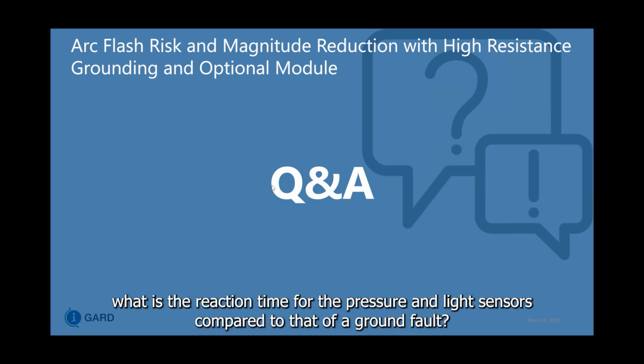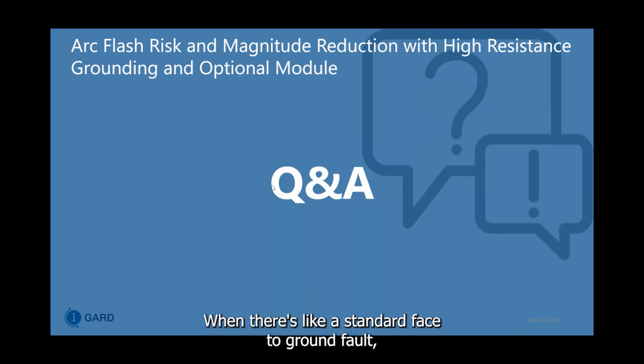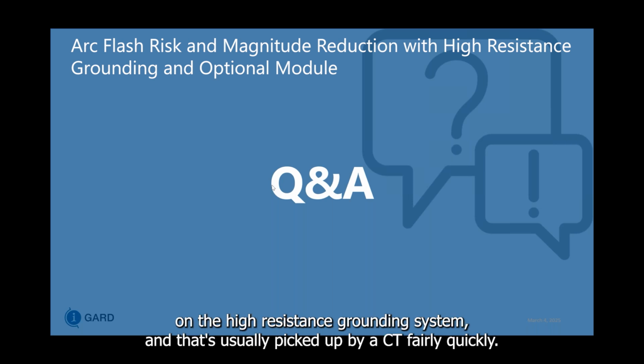What is the reaction time for the pressure and light sensors compared to that of a ground fault? When there's a standard phase to ground fault, we are usually picking up neutral voltage and neutral current on the high resistance grounding system, and that's usually picked up by a CT fairly quickly.